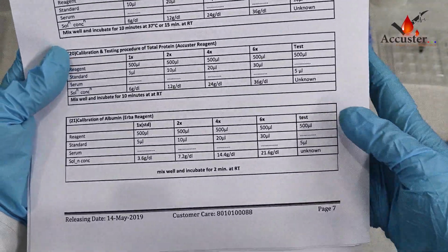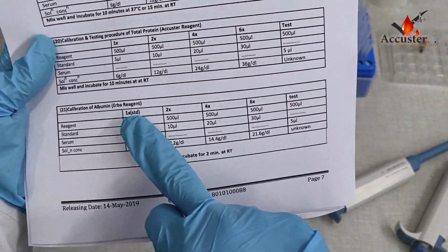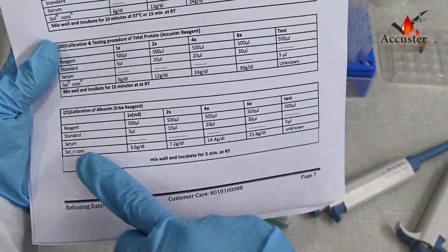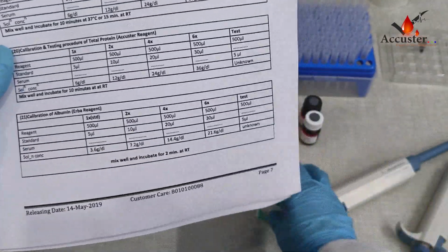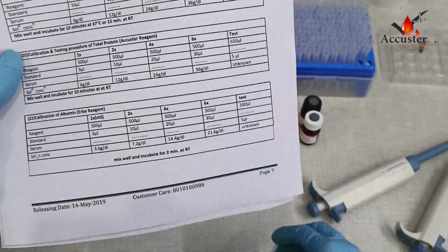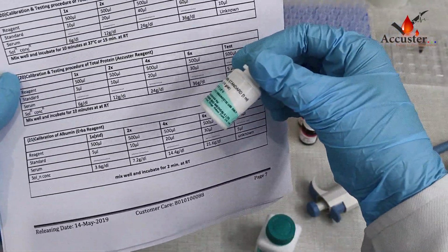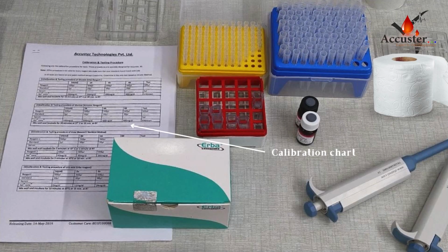Here is the procedure for albumin test calibration. Requirements for albumin test calibration are albumin test reagent kit with standard, calibration chart, 2 micropipettes, one large of 100 to 1000 microliters and one small of 5 to 50 microliters. Micropipette tips both large and small. Tissue paper, and now let's begin with the calibration procedure.